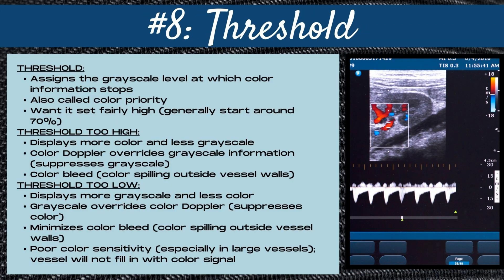The next control in our color Doppler optimization checklist is the threshold setting. The threshold assigns the grayscale level at which color information stops — also called the color priority control — and you want this set fairly high, generally starting around 70%. When the threshold is set too high, it displays more color and less grayscale; the color Doppler information overrides and suppresses the grayscale, and this is when color bleed — color spilling outside of vessel walls — can occur. When the color threshold is set too low, it displays more grayscale and less color; the grayscale overrides and suppresses the color, minimizing color bleed but resulting in poor color sensitivity, especially in large vessels which will not fill in with a color signal.